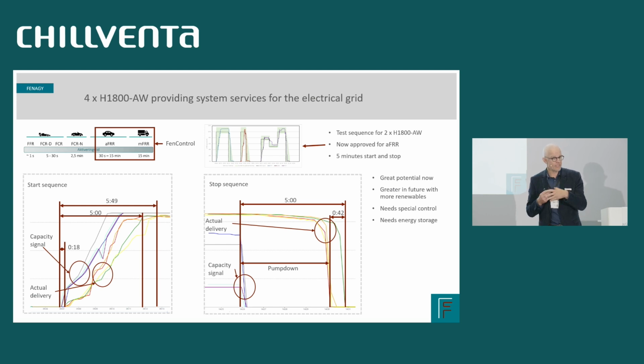If you are either a producer of electricity or a consumer of electricity, you get paid to help the electrical grid every second. So to be on the very fast track here, normally heat pumps are working in this area of 15 minutes. We need to make the heat pump much faster so we can frequency regulate the electrical grid with very fast stop-starting of compressors. So that's what we are aiming at, getting down to, FCR is 30 seconds, and that's what we are aiming at with our heat pumps.